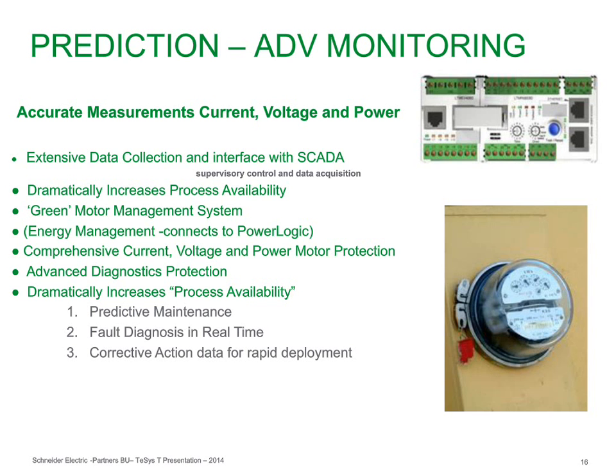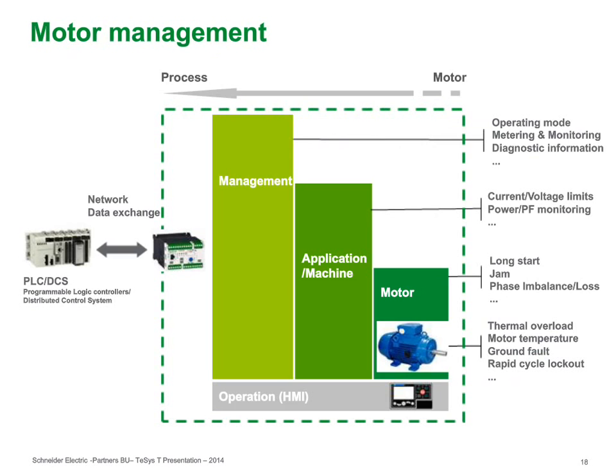So from a design standpoint, you've told me a lot of information in the last 20 minutes about what it can do, but how do I actually apply this to make sense for my applications and my processes? And there's probably three stages here. The first one is the main purpose of an overload relay is to protect the motor winding. And having a solid state overload does that very, very well because it's not heat sensitive. So it will be very, very repeatable in the points that it trips.